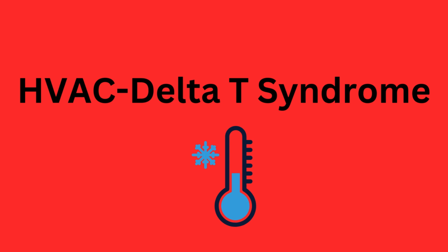Symptoms of delta T syndrome: insufficient cooling. The system fails to cool the space effectively, leading to uncomfortable indoor temperatures. Increased energy consumption. The HVAC system works harder to achieve the desired temperature, resulting in higher energy bills. Frequent cycling. The system cycles on and off more frequently than normal, indicating inefficiency.